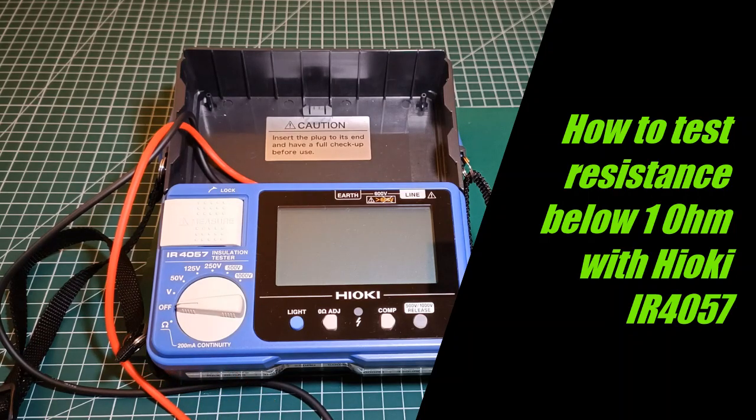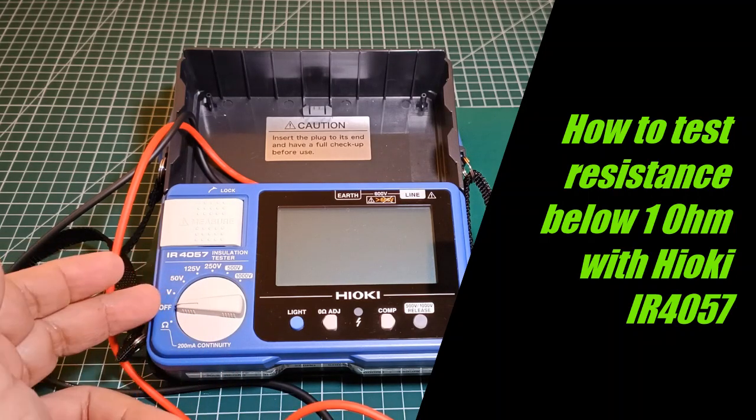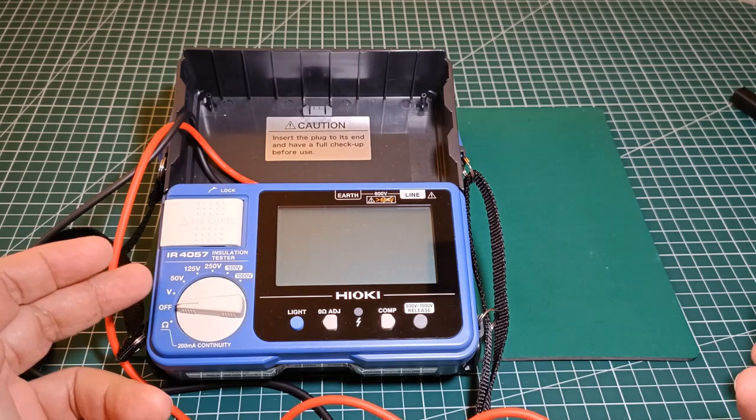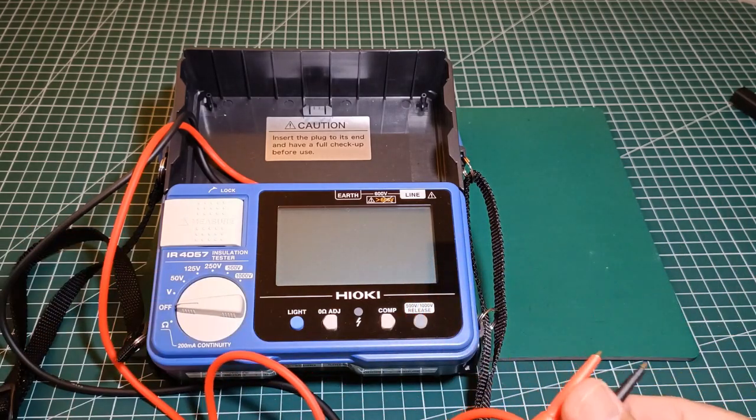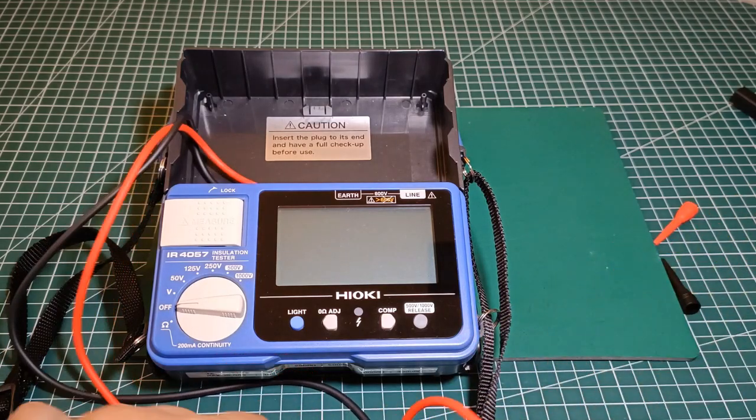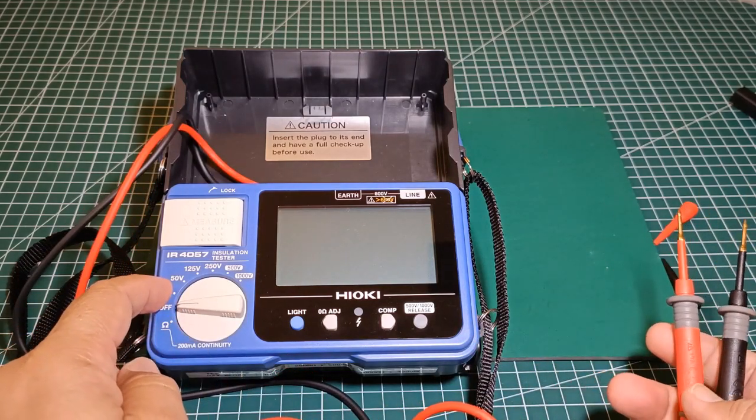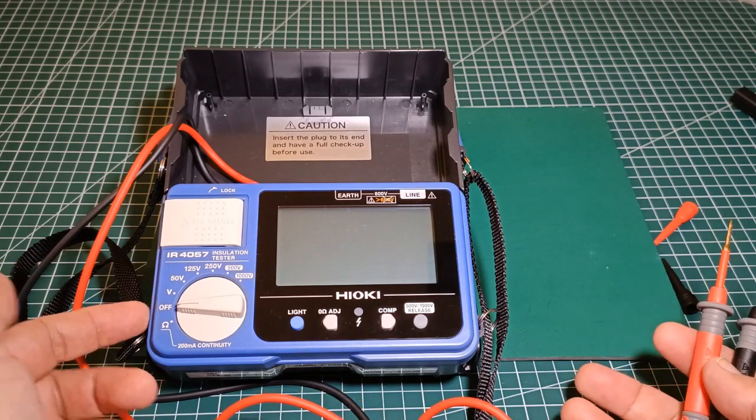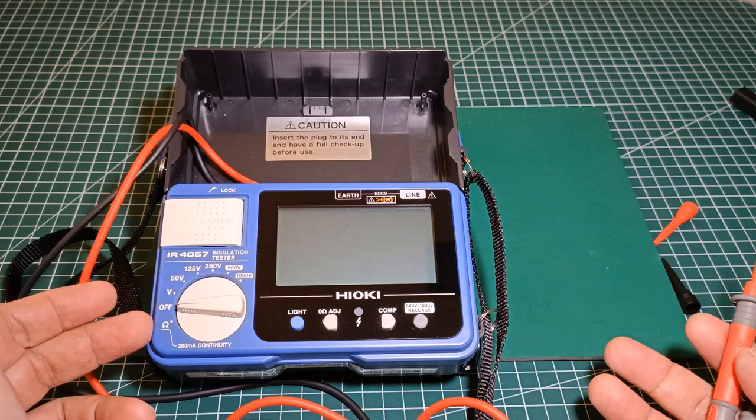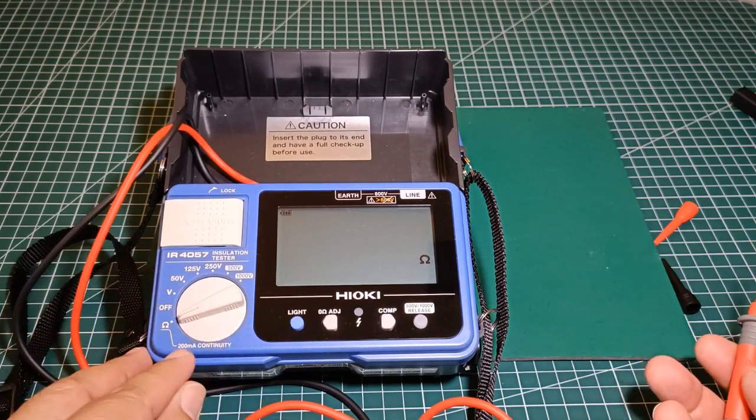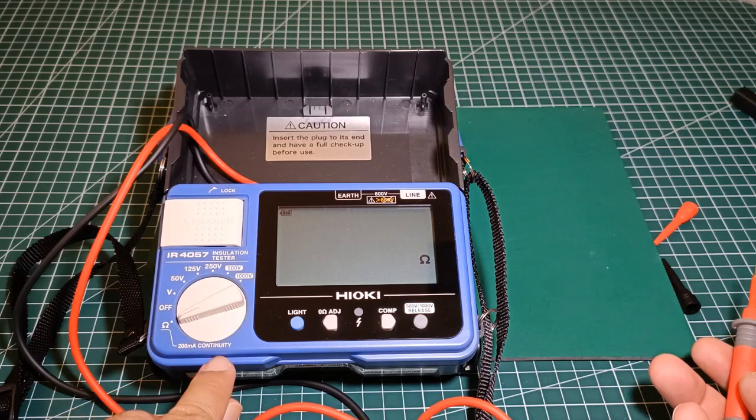Hello everyone, this is the Hioki IR4057 insulation tester. As you know, the main purpose of this insulation tester is to measure insulation resistance, of which the maximum capability of this tester is 4000 megaohms. But perhaps a lesser-known function of this insulation tester is its low resistance measurement function, here at the 200 milliampere continuity function.